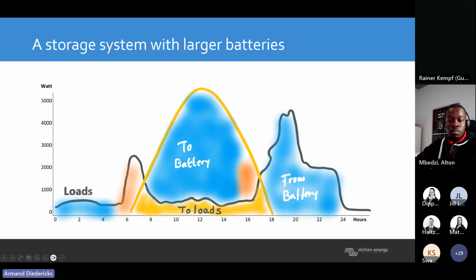All right, exactly the same for a storage system with larger batteries. If you've got a larger battery bank and your loads stay low, the PV grid tie inverter or the MPPTs can charge the battery on this side and take over the loads. And during daytime or nighttime, when there's no sun available, it can provide power to your loads on the battery side, depending on what TOU, time of use tariff, you are on.